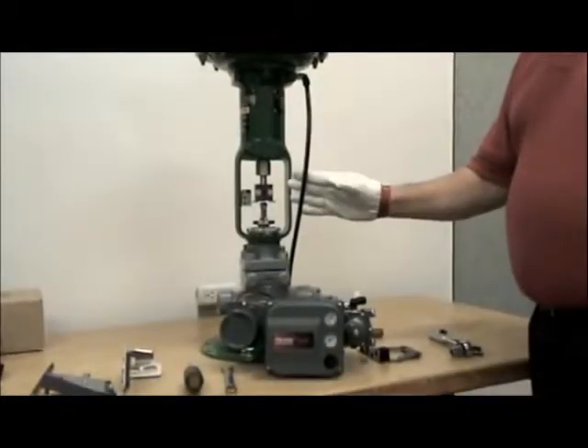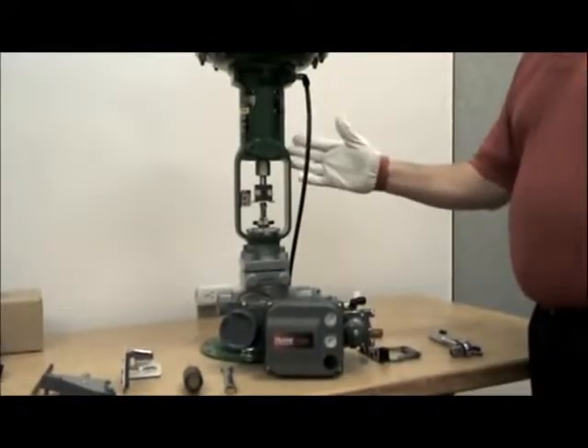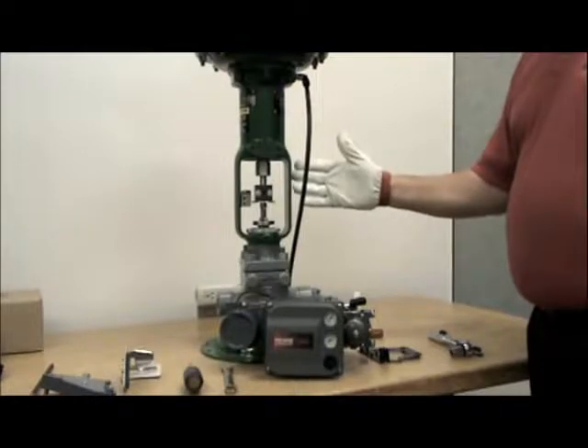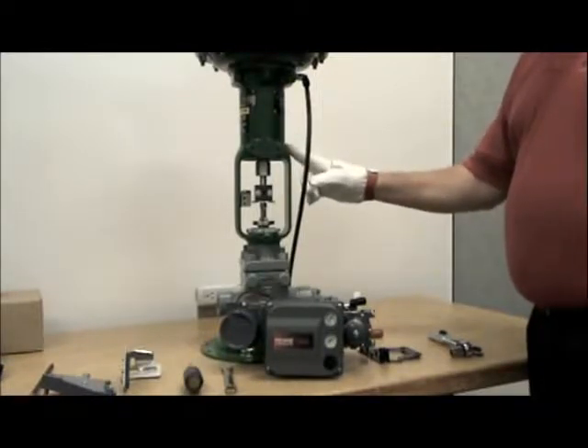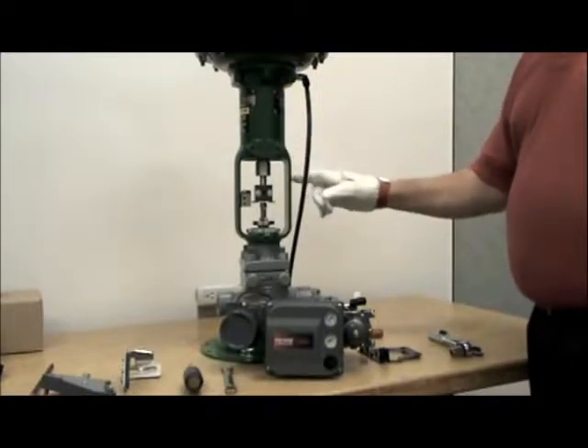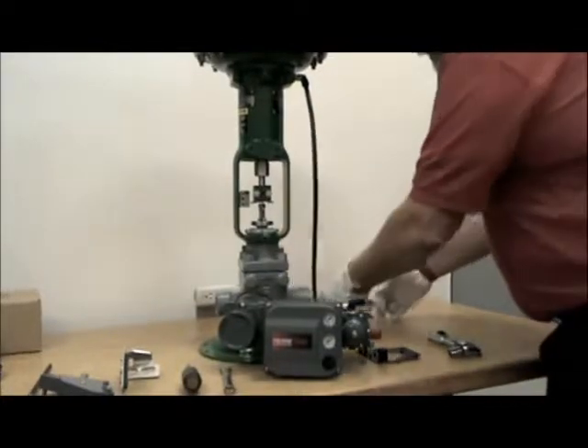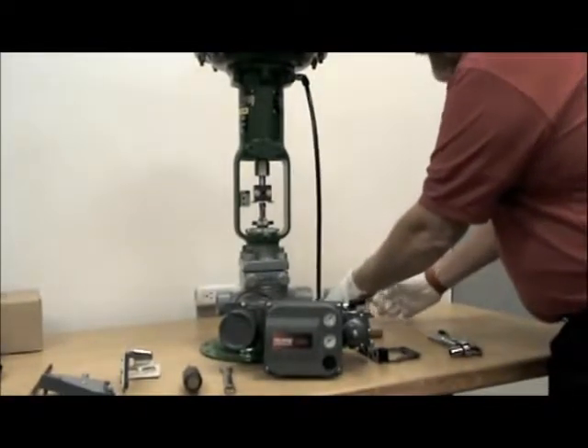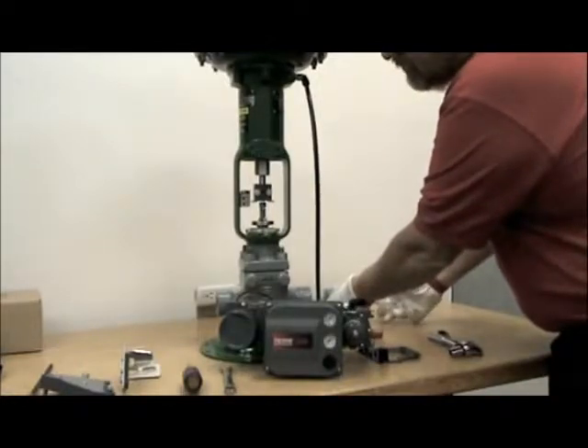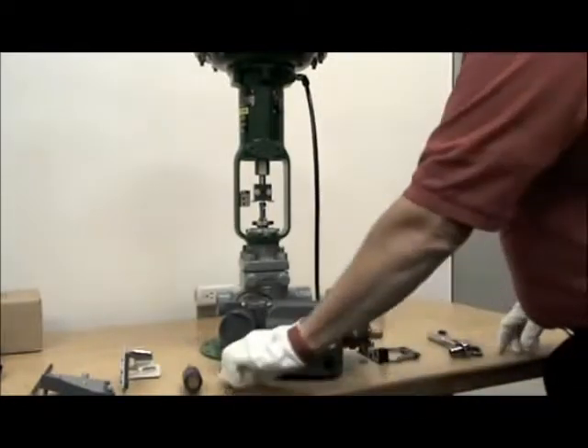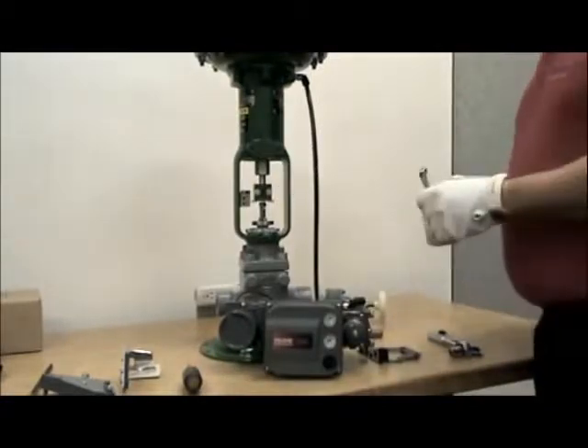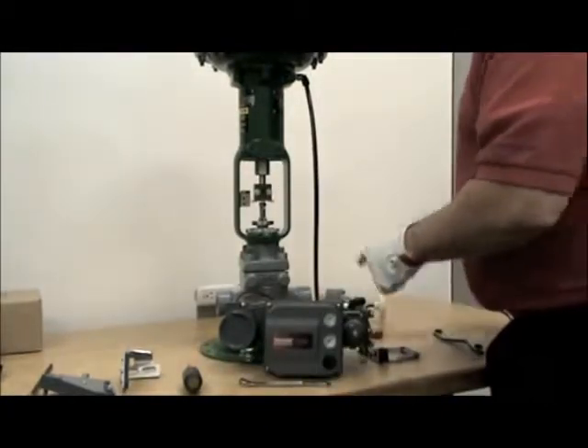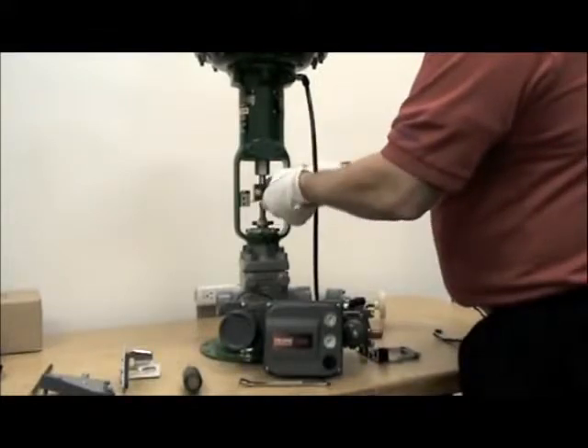Now before we can uncouple the actuator, we need to take some of the actuator load off the plug. Because this is a 667 Fisher actuator, it is spring closed. We're going to add some air to the actuator and make sure the valve plug moves up off the seat. Once it's off the seat, we'll overcome the force of the spring and balance it with air pressure.